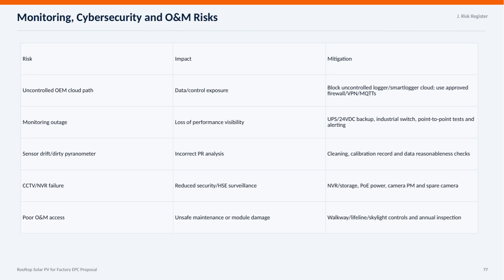Next, monitoring outages can cause loss of performance visibility, which we address by implementing backup power supplies, industrial switches, and alerting through point-to-point tests. Sensor drift or dirty pyranometers can lead to incorrect performance ratio analysis, so regular cleaning, calibration, and data reasonableness checks are essential. CCTV and NVR failures reduce security and health safety surveillance, which we mitigate by maintaining storage, power supplies, preventative maintenance, and having spare cameras ready.